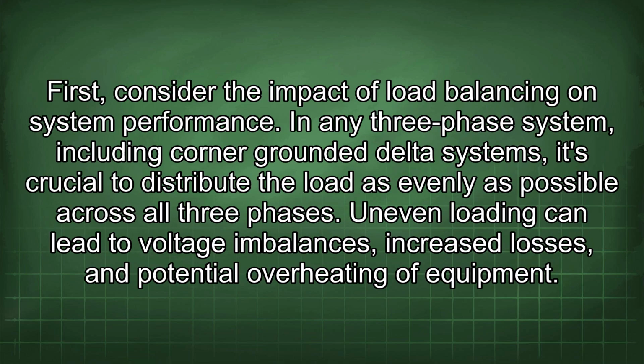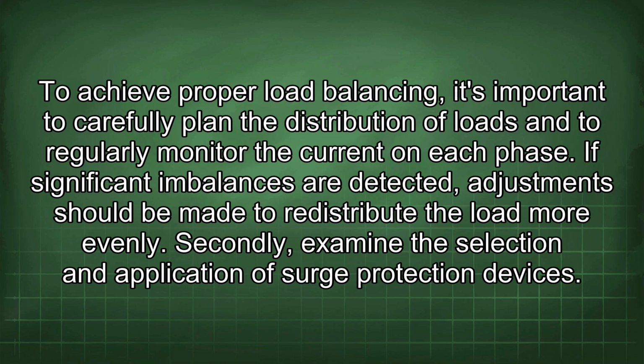First, consider the impact of load balancing on system performance. In any three-phase system, including corner-grounded delta systems, it's crucial to distribute the load as evenly as possible across all three phases. Uneven loading can lead to voltage imbalances, increased losses, and potential overheating of equipment. To achieve proper load balancing, it's important to carefully plan the distribution of loads and to regularly monitor the current on each phase. If significant imbalances are detected, adjustments should be made to redistribute the load more evenly.